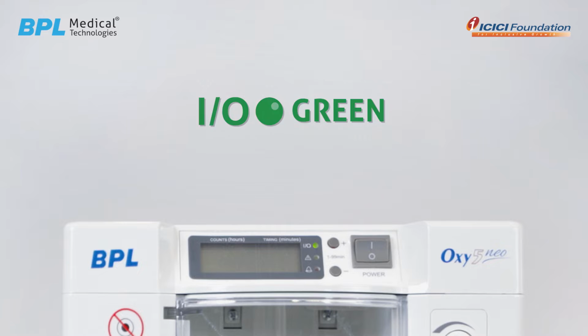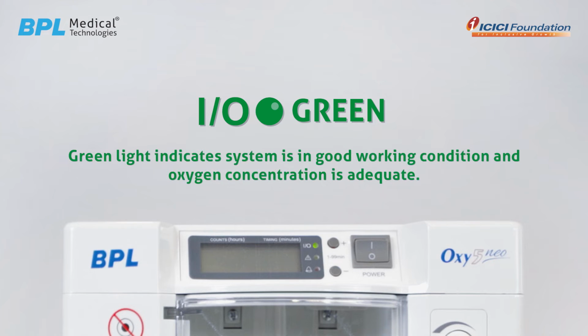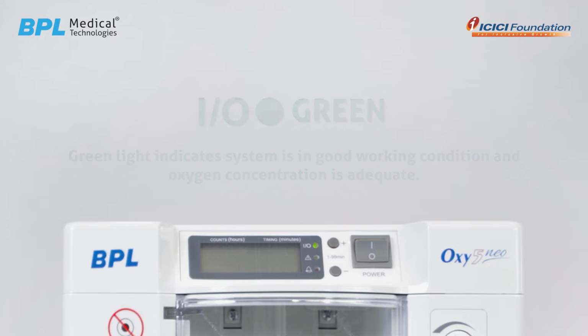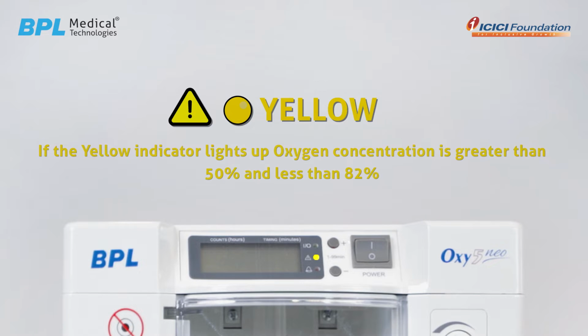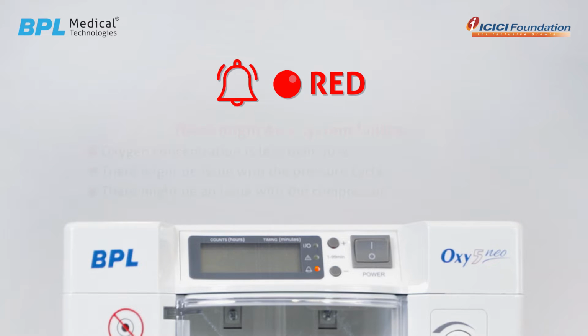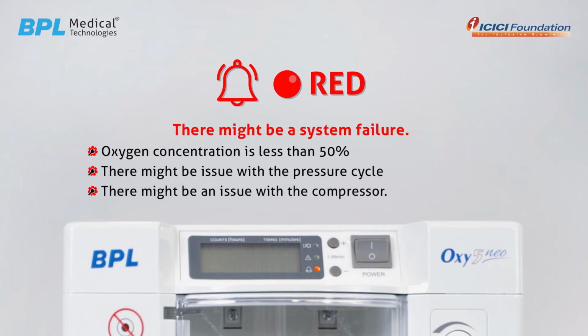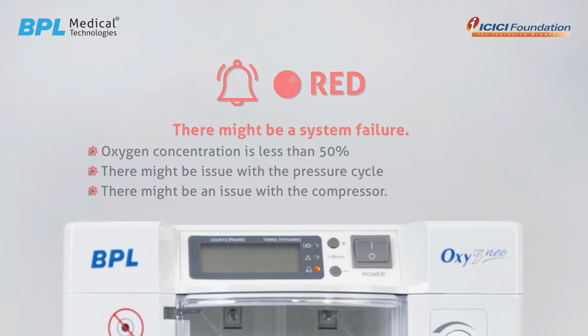The explanation of indicator lights. Green light indicates system is in good working condition and oxygen concentration is greater than 82%. If the yellow indicator lights up, oxygen concentration is greater than 50% and less than 82%. If the red indicator goes up, then there is a system failure where the oxygen concentration is less than 50% and there might be an issue with pressure cycle and the compressors.